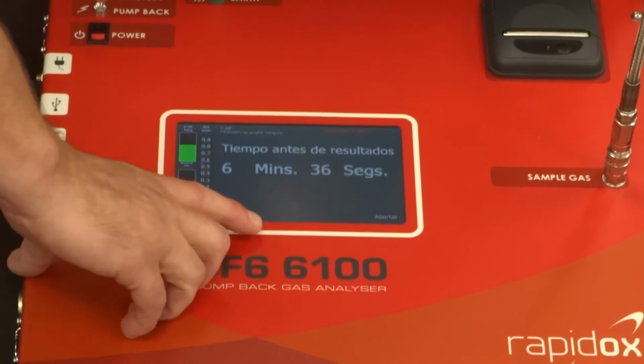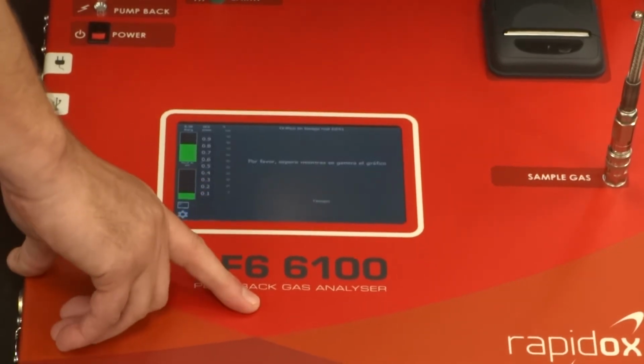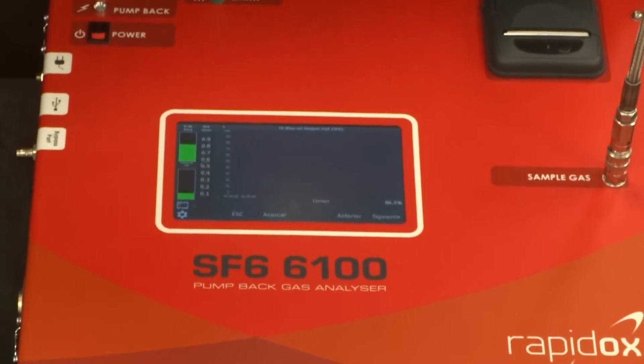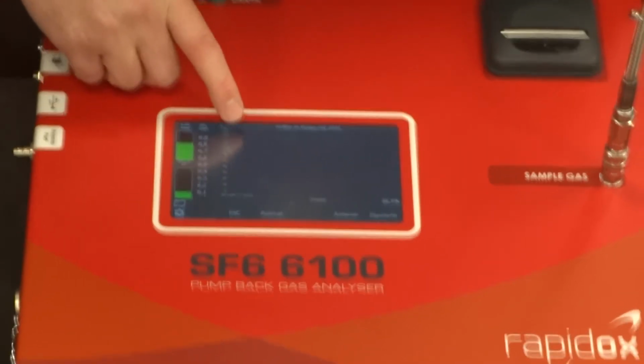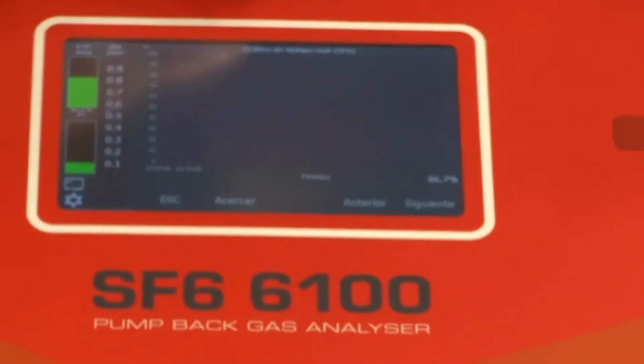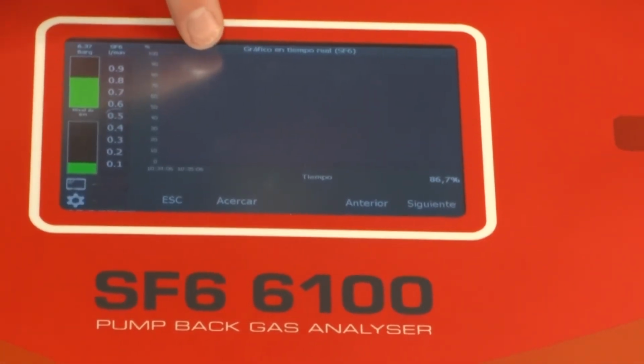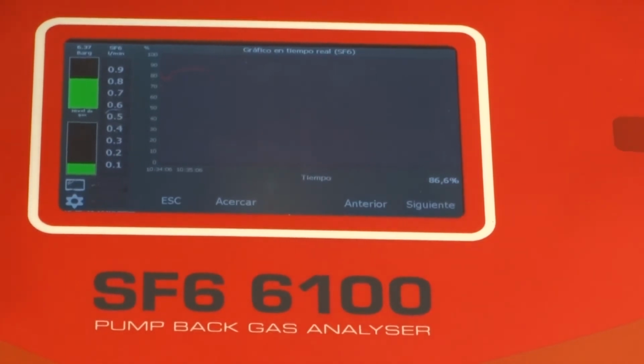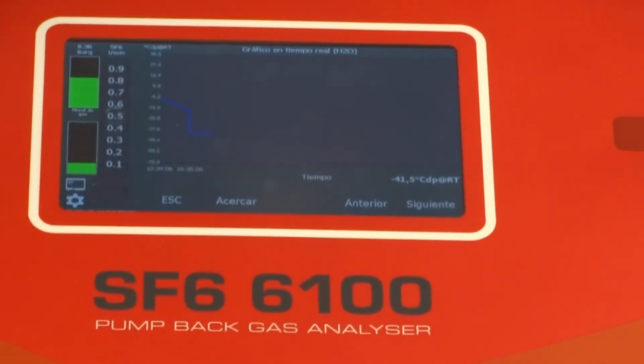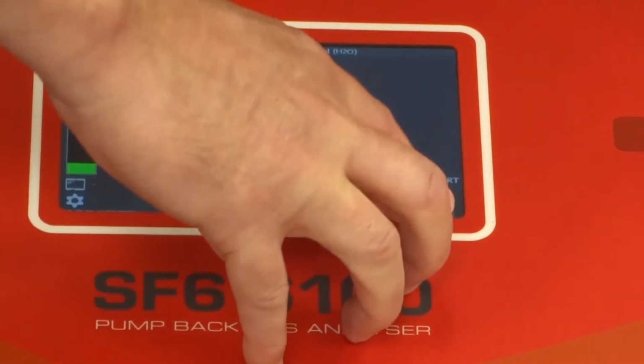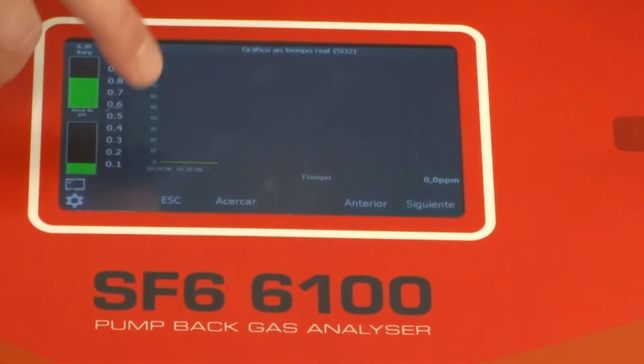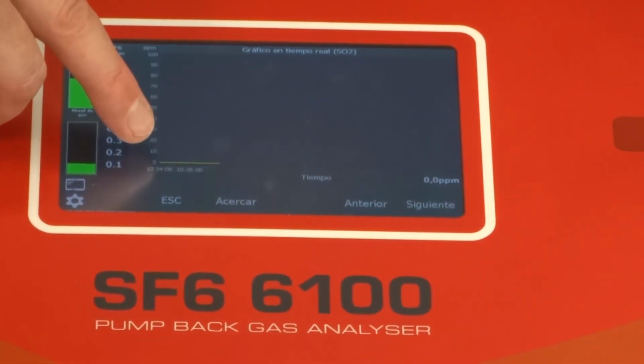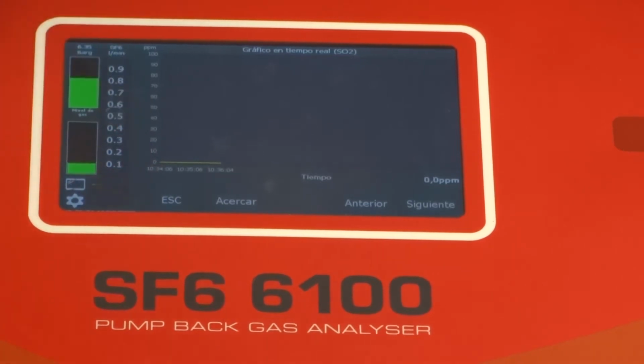So one thing you can do is press the graph button while the test is proceeding, and you can see that there's a live time display, and this one is SF6. So here it's coming up to about 80 or 90% SF6. If I press next, I can see a blue trace, which is the water reading, which is currently at minus 42 degrees CDP. And the third trace is the SO2. Now there is no SO2 in this gas, so this reading is 0.